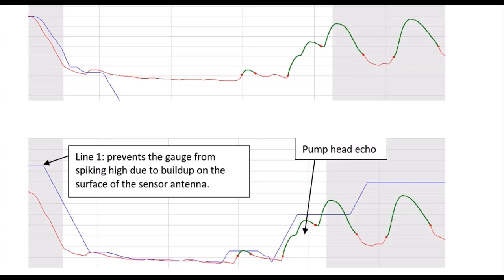You're going to go into an area called false signal suppression. I'm going to demonstrate this to you in just a few moments. You're going to carry out a false signal suppression. That's step one. And then under the false signal suppression tab, there's an edit tab. And the edit tab is where you can custom build the false signal suppression to eliminate these problems. The automatic false signal suppression will only get you halfway there. You have to put the manual edits in next.